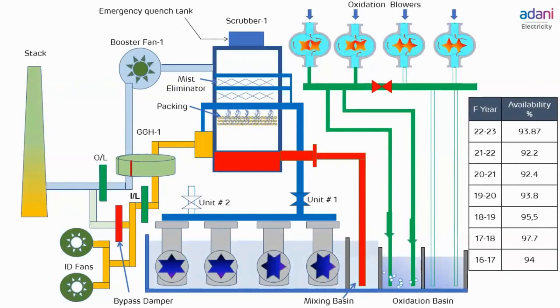The subcooled flue gas from GGH enters horizontally at the bottom of the seawater scrubber. This scrubber is a square vertical concrete vessel with FRP, GRP, GRE lining designed to withstand long-term contact and corrosive effect of a hot acidic brine. The seawater is sprayed counter current to the flow of flue gas at the top of the surface packed bed in order to achieve effective SO2 mass transfer and absorption in liquid phase. The seawater is sprayed through specially designed spray nozzles distributed in such a way as to uniformly cover the maximum surface area of the packed tower.